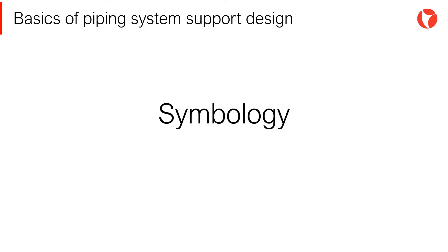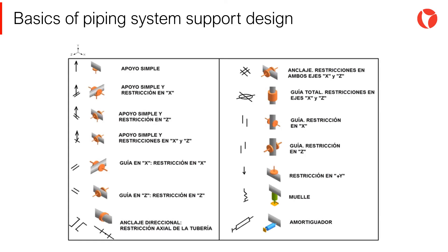The supports selection process is an iterative process in which the designer studies the system restrictions and proposes a configuration for the supports. This configuration is then evaluated by the flexibility analyst, who generates a flexibility isometric by ratifying or rectifying the design of the proposed supports. Since this process is iterative, it is necessary to have a clear and simple symbology to assist communication between the parties involved. As seen on the screen, all types of supports can be combined, resulting in supports performing different functions simultaneously.